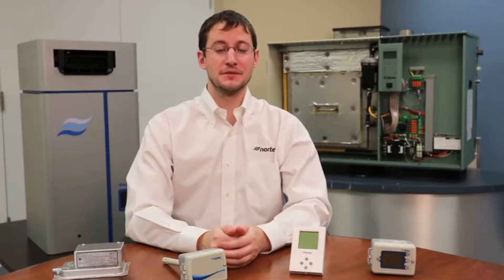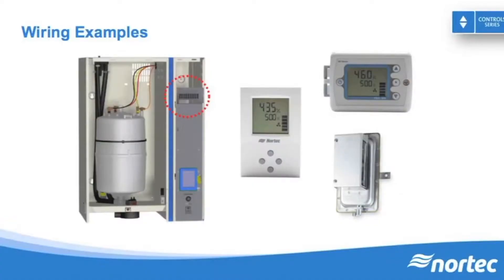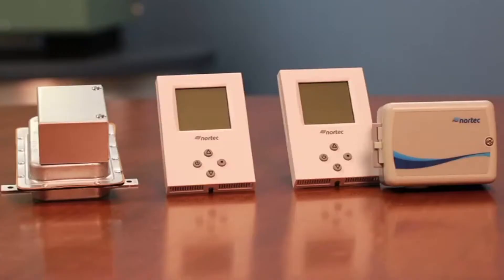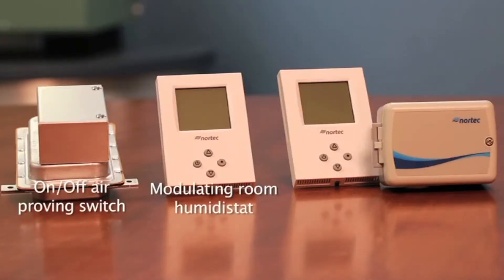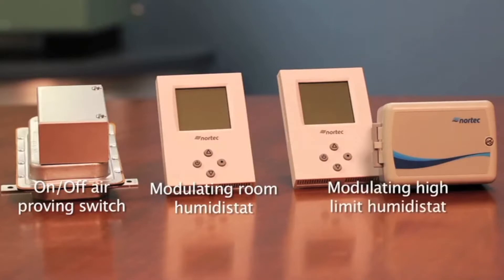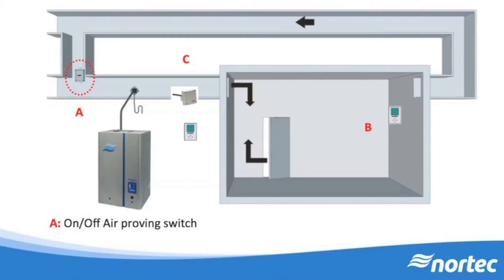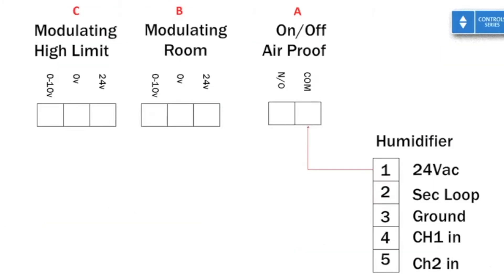Now that we've explored the three main controlling devices, we can see that there are various possibilities. We'll take you through various examples to make sure you have a better understanding of how to wire these devices. Consider the following three specific devices: an on-off air proving switch, a modulating room humidistat, and a modulating high limit humidistat. The on-off air proving switch starts from 24 volts AC on the humidifier's low voltage terminal strip, typically pin 1.